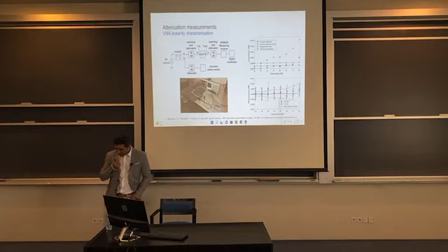For that, we need to have a primary setup that measures the attenuations much more accurately than a VNA. So here you see a dedicated setup which we designed for attenuation measurements. This system can calibrate attenuations up to 80 dB with 10 millidB accuracy. So that's pretty good. But that's what you need to calibrate, for example, automated attenuators, which are subsequently used to characterize the linearity of your VNA.